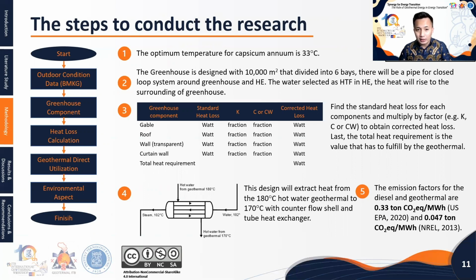After that, find the standard heat loss for each component, then multiply by each factor to obtain the corrected heat loss. Last, the total of the corrected heat loss will be the minimum heat required for the geothermal to supply. This design will extract heat from Wayang Windu at only a 10 degree temperature decrease, from 180 to 170, with counterflow shell and tube heat exchangers. The counterflow is suitable to get a lower area for this case when compared with the parallel flow. Moreover, the emission factors for diesel and geothermal are 0.33 ton carbon dioxide equivalent per megawatt hour and 0.047 ton carbon dioxide equivalent per megawatt hour.